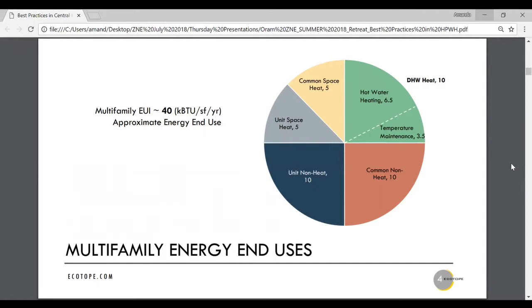That's the heat, that's the central hot water heating system. A further breakdown is about 3.5 EUI, or about 35%, associated with what we call temperature maintenance, which is keeping the pipe hot. So that's a third of your energy just maintaining the loop. The other two-thirds is the actual physical heating of the water. Before we started down this path trying to understand this, we had no idea what this temperature maintenance piece was, and everyone else thinks it's a 15-20% problem. No, it's way bigger - I've seen this be equal to the hot water load.